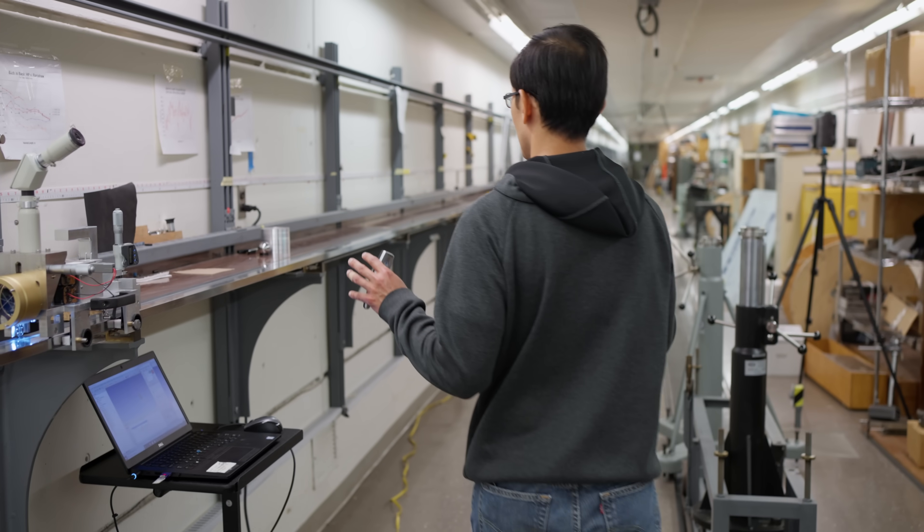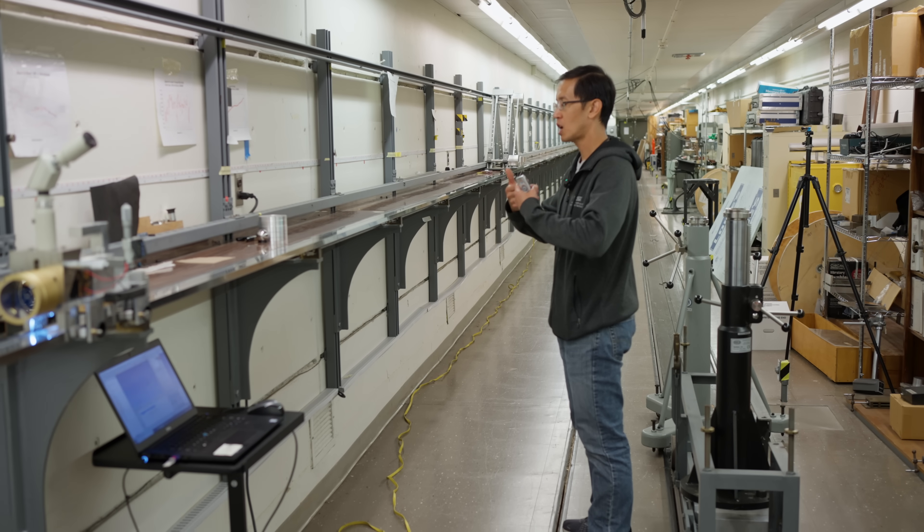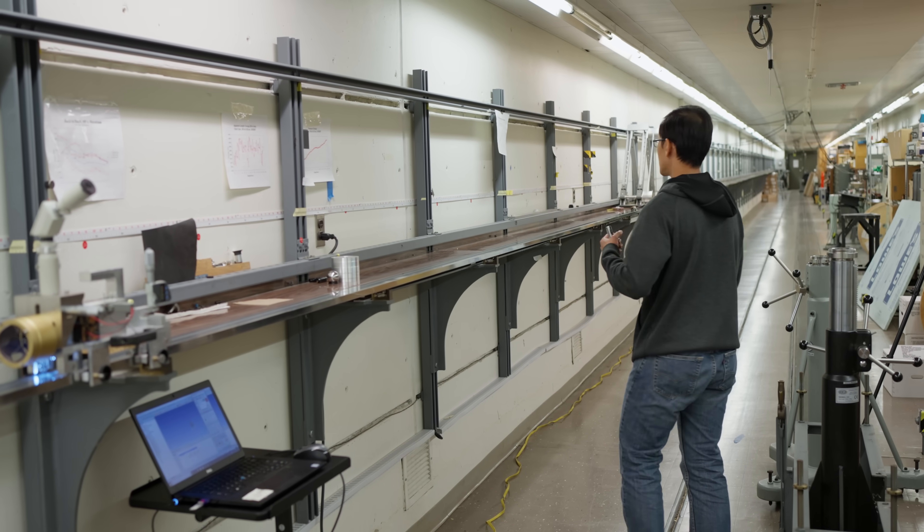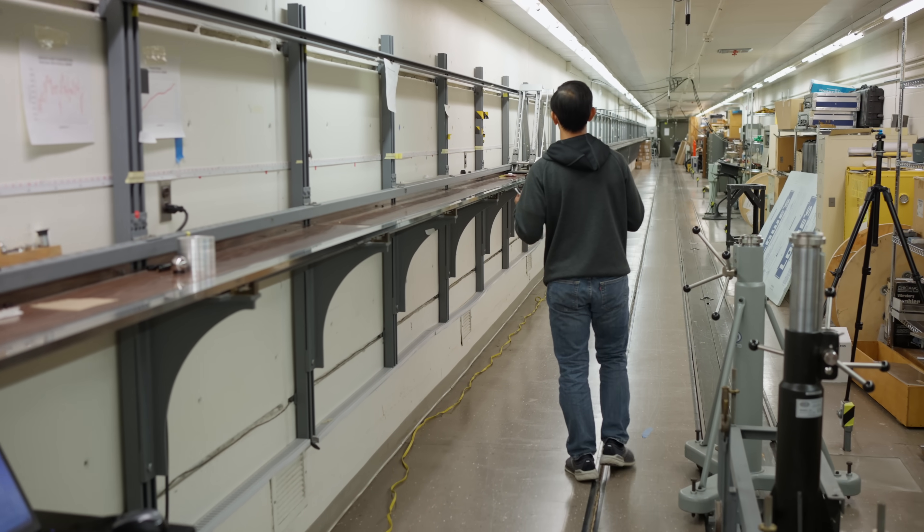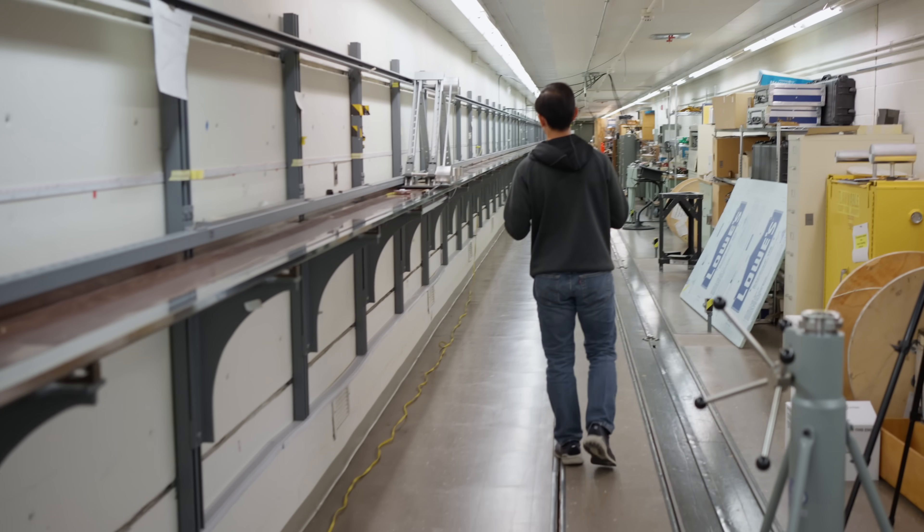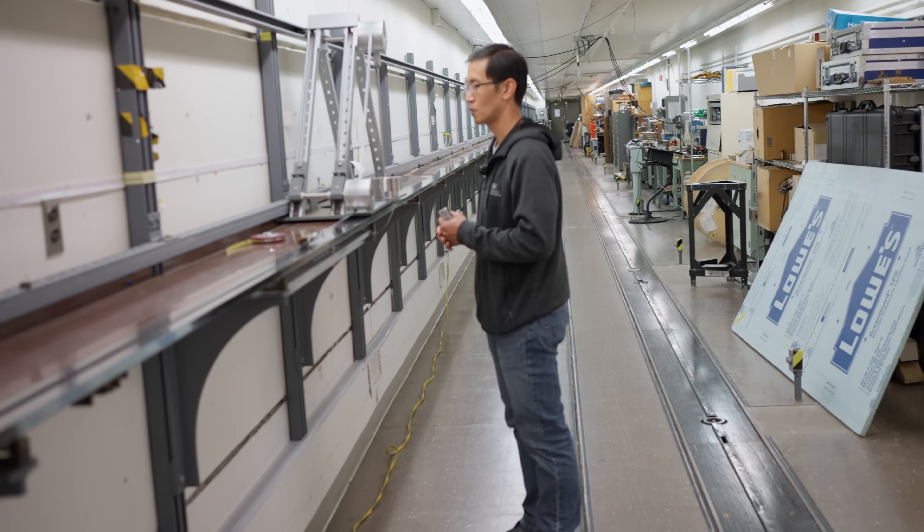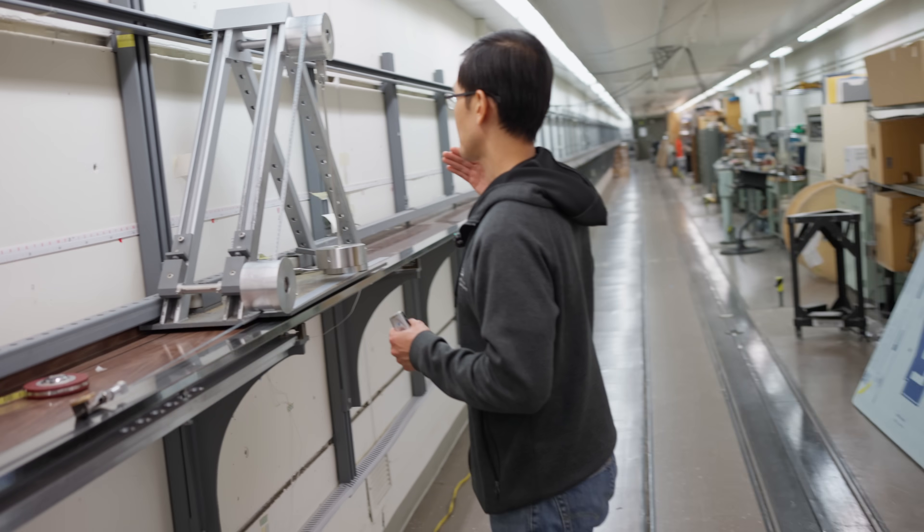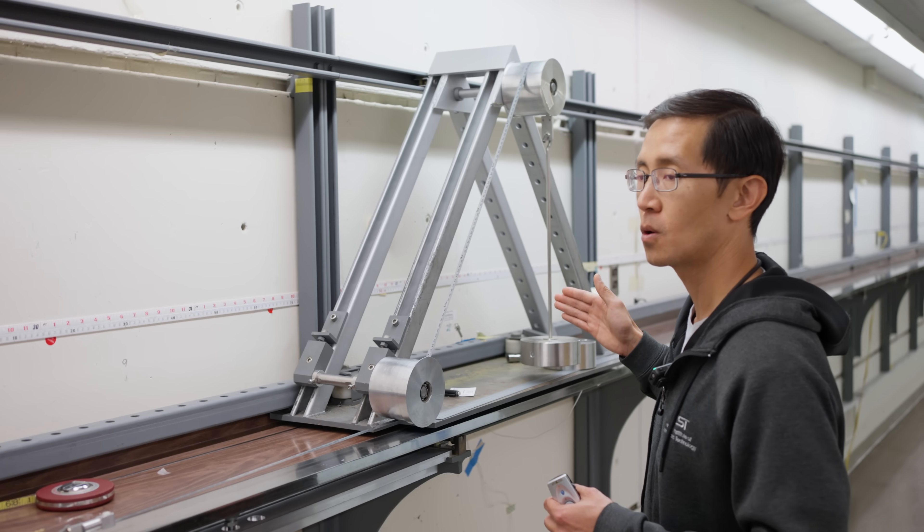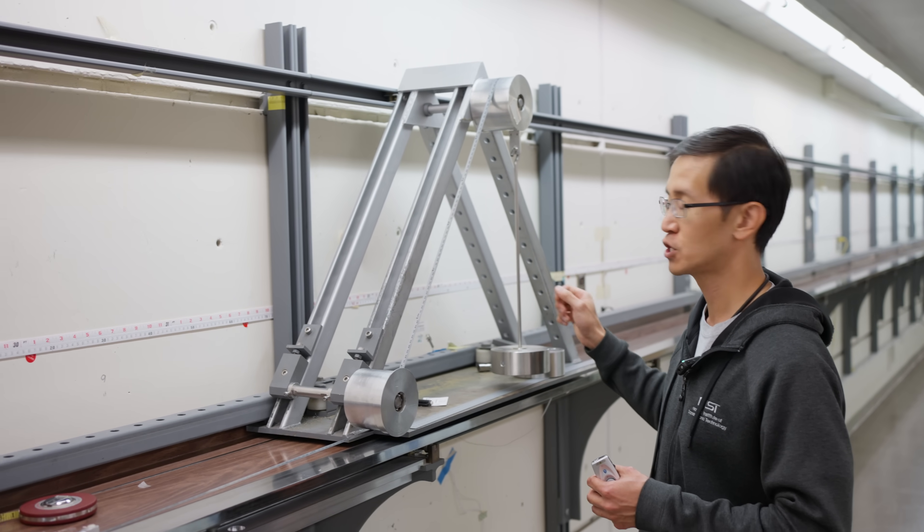A lot of tapes have to be tensioned in order to achieve the proper graduation spacing. In the ASME specifications, not only do they specify MPE, but they specify an amount of tension that should be placed on the tape when it's being measured or used or calibrated. And for tapes that are 100 feet or 30 meters long or less, a tension of 10 pounds or 5 kilograms, respectively, should be applied to it.